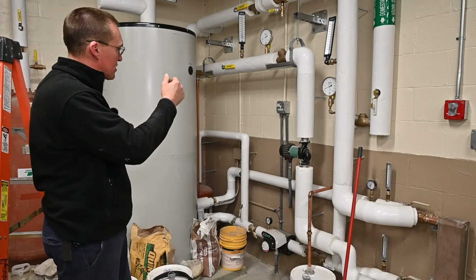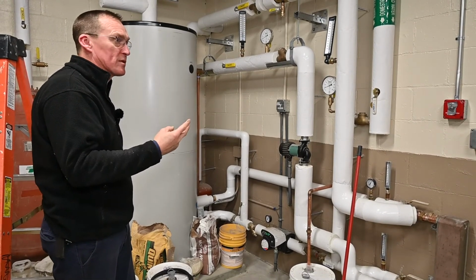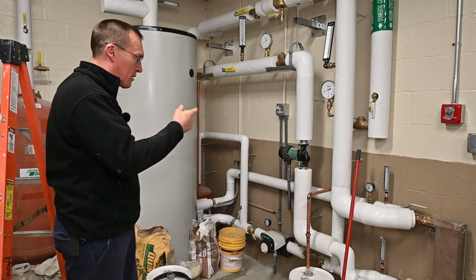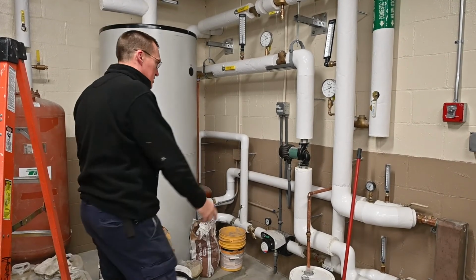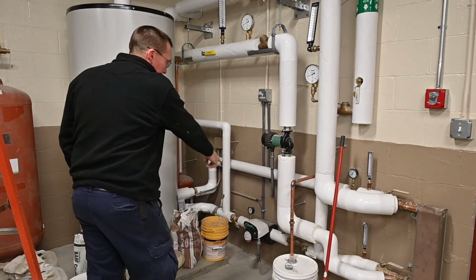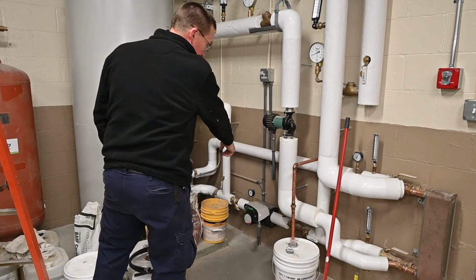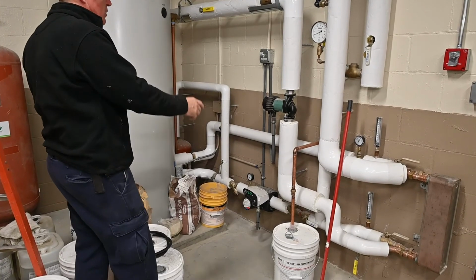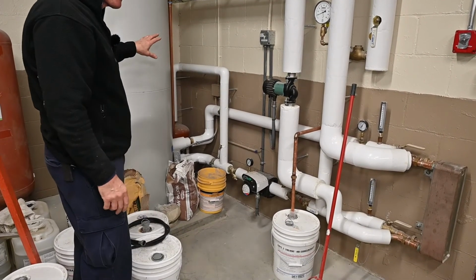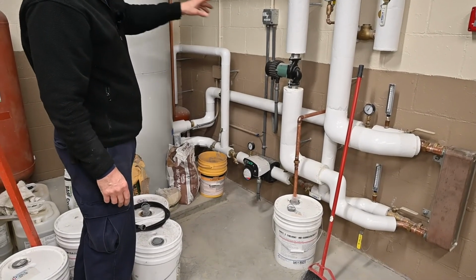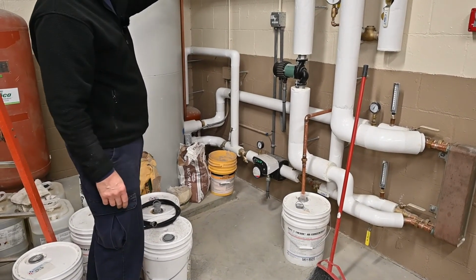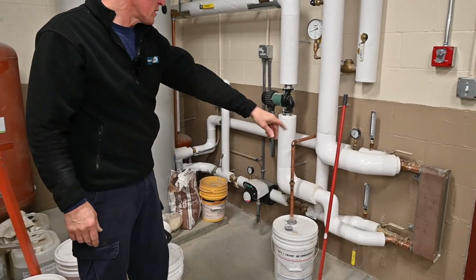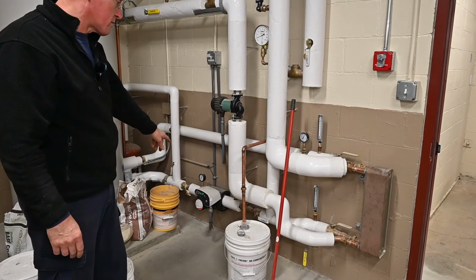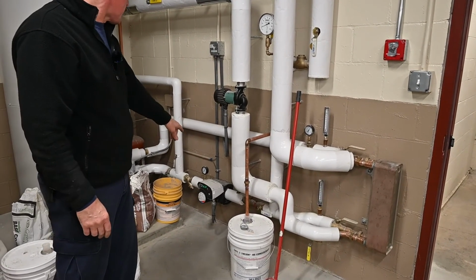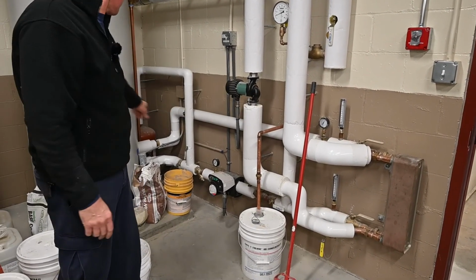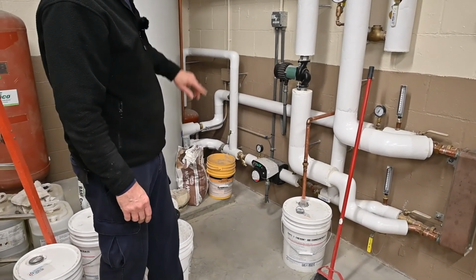And those 2.5-inch pipes come into the Zamboni room, where you have 2 pumps. You'll see those switches on our main panel in front, called P7, which is this small circulator here, and P10, which is the city water circulator here. Basically, once the chiller plant starts and you're running one of the heat pumps, P7 will start.